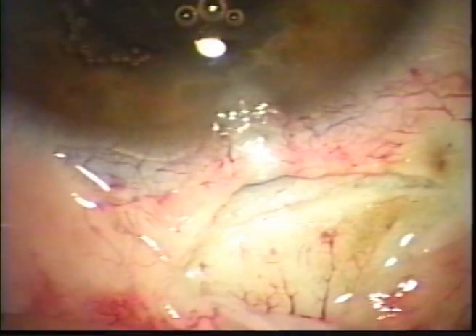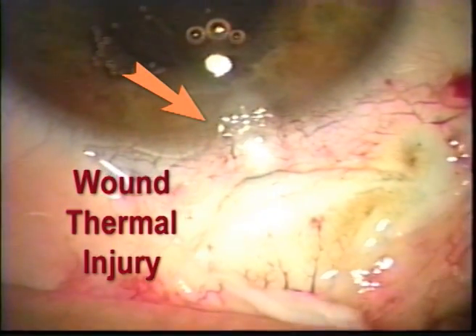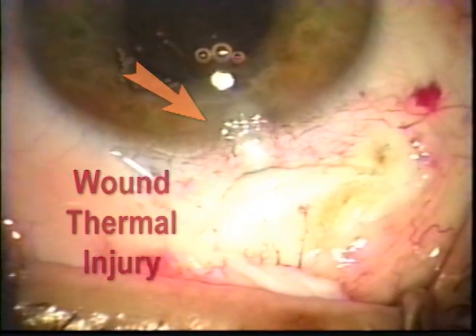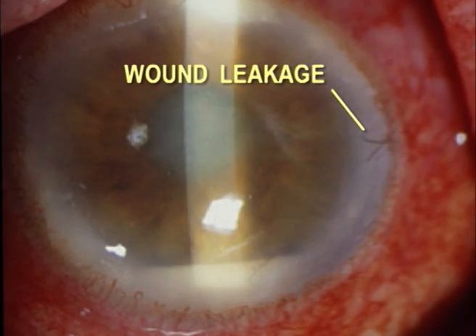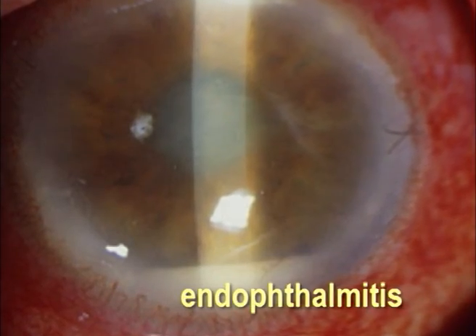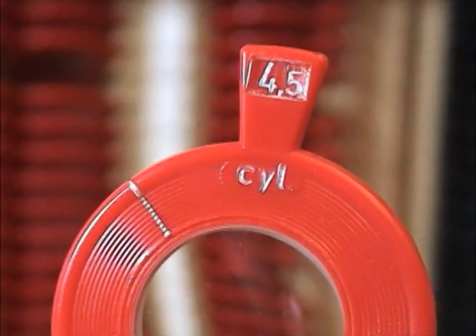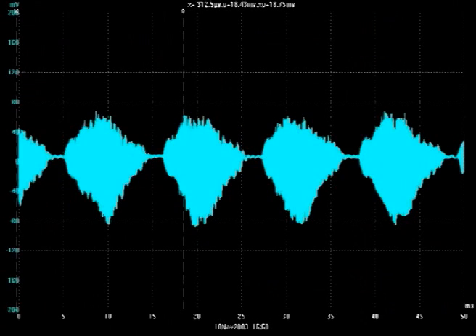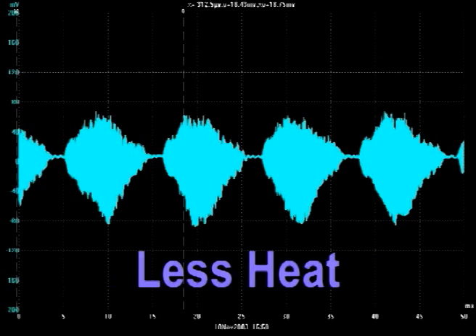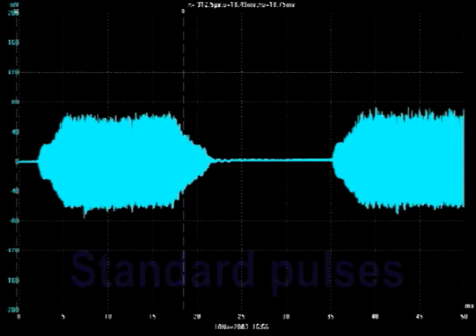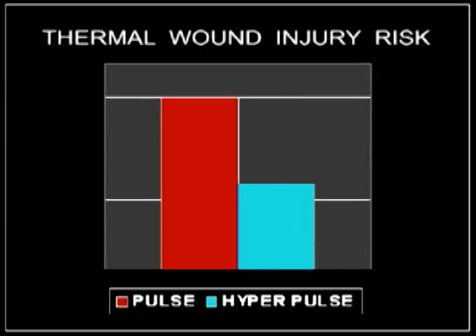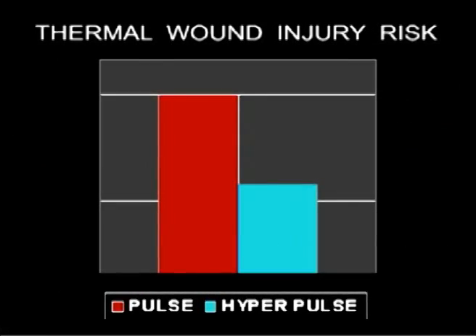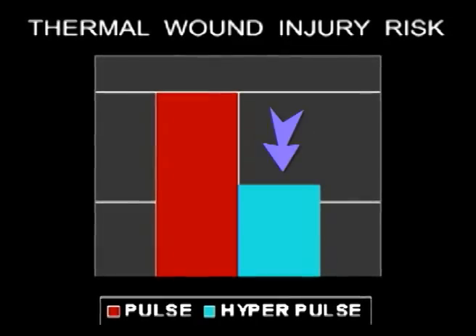The main thermal consideration of modern phaco is the risk of producing a burn at the incision site, increasing the chance of complications, and reducing the visual outcome due to induced astigmatism. It has been claimed that hyperpulses would dissipate less heat at the incision site than standard pulses on an isopower basis, reducing the risk of thermal injury.